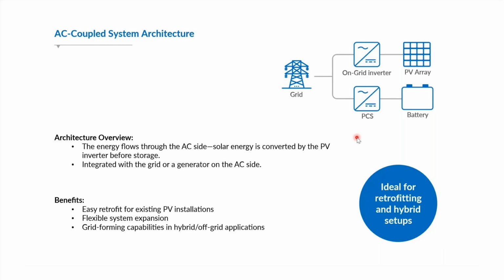It's also excellent for hybrid setups, where you might be switching between grid supply, solar input, or generator backup. There's a bit of an issue here, not critical, but worth mentioning - you'll encounter some efficiency losses because the power gets converted multiple times, from DC to AC and then from AC back to DC for storage, and this includes some conversion losses. But in exchange you get flexibility, system level independence, and a much easier path to expand or integrate into commercial or multi-source systems. So when the goal is to add storage to an existing site or work with grid parallel designs, AC coupled systems are the solution to go.